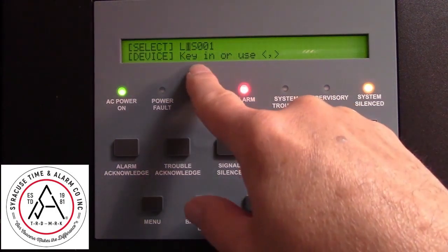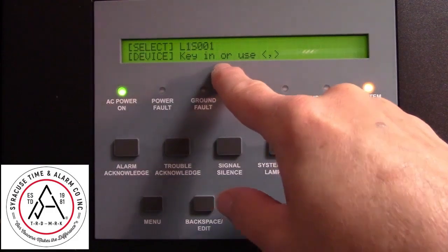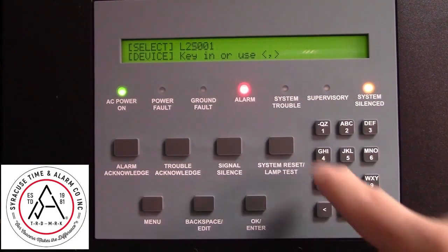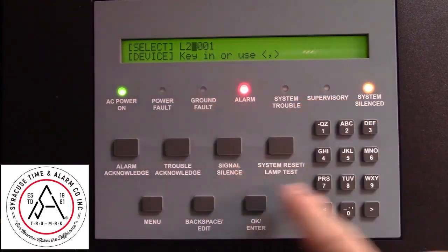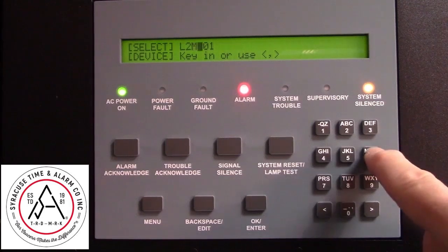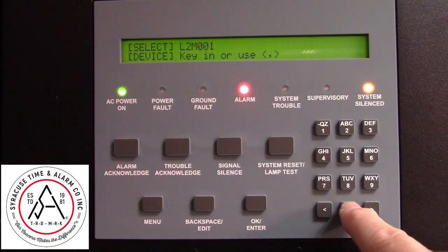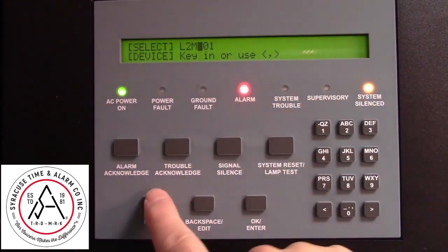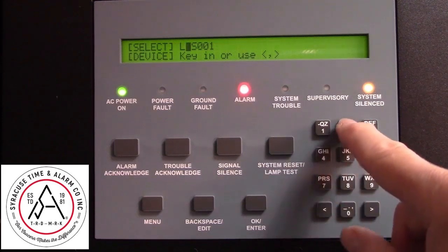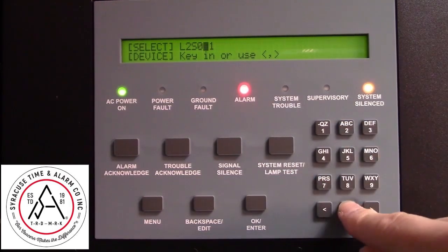Now remember that device was address Loop2S001. Change that to a 2. If the address was a monitor, you press the 6 button, which has the M, and then you can put in the address. If you accidentally change that, you can back out and start over again. Loop2S001.